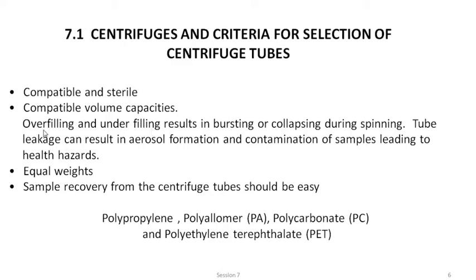Both overfilling and underfilling will result in bursting and collapsing during spinning. When you go on spinning, if you have filled one tube half and the opposite tube full, it will burst your centrifuge tubes and sometimes it will spill out. So whatever you do will become a waste, and tube leakage can result in aerosol formation, you know that, and contamination of the samples leading to health hazards.